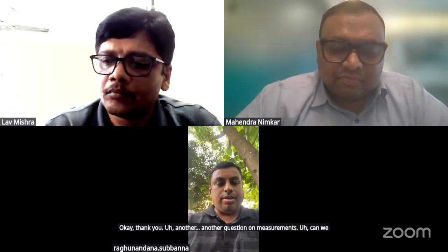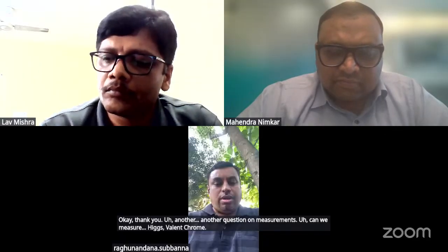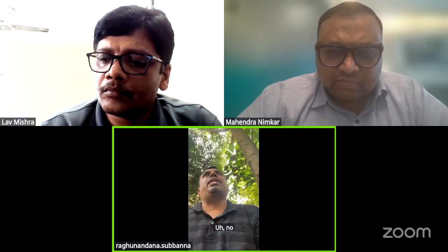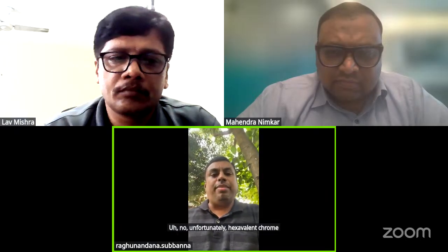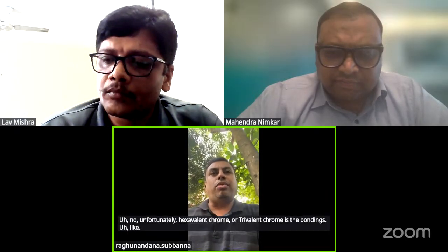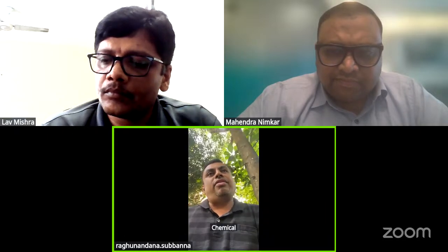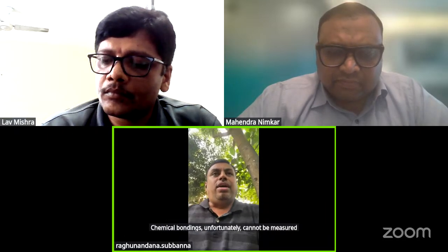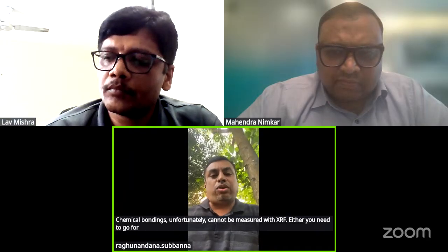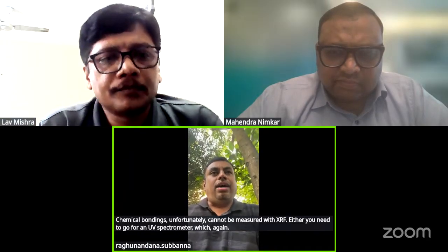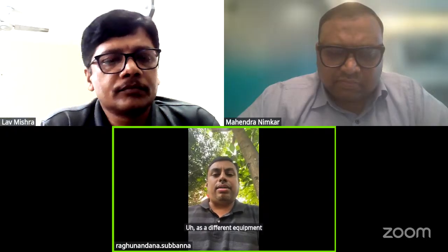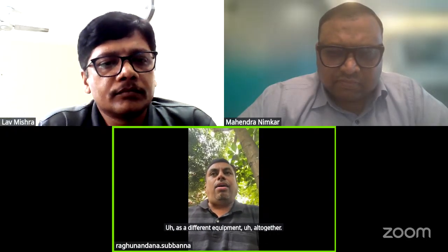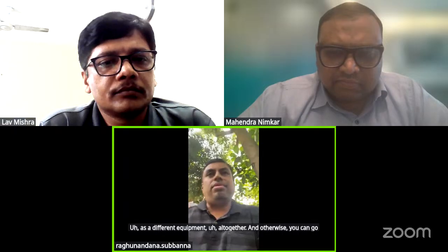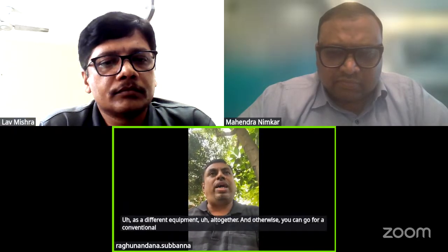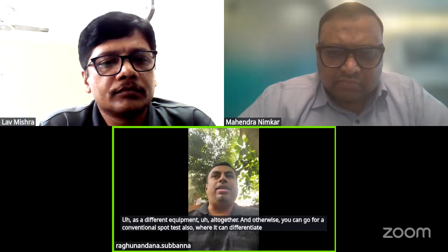Another question on measurements. Can we measure hexavalent chrome? No, unfortunately, hexavalent chrome or trivalent chrome refers to chemical bondings, and chemical bondings cannot be measured with XRF. Either you need to go for a UV spectrometer, which, again, is a different piece of equipment altogether, or otherwise you can go for a conventional spot test, which can differentiate between trivalent and hexavalent.